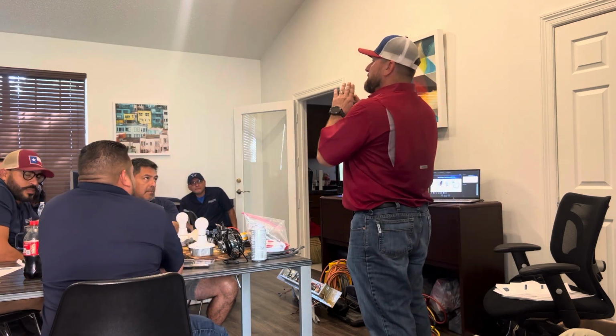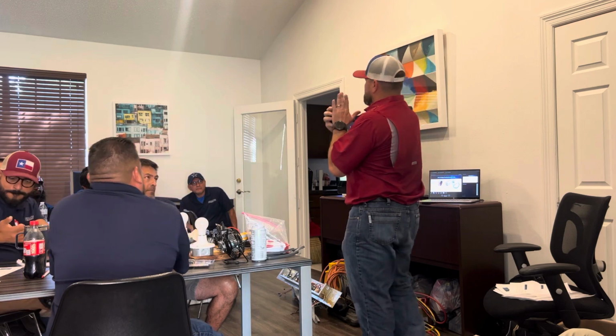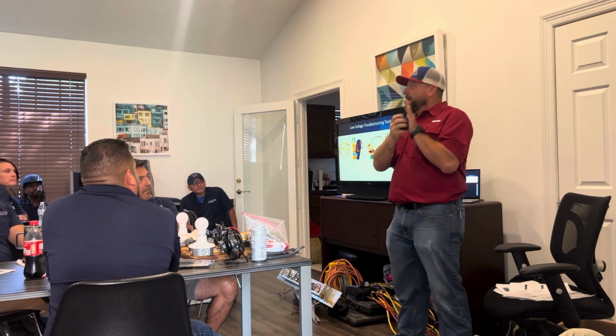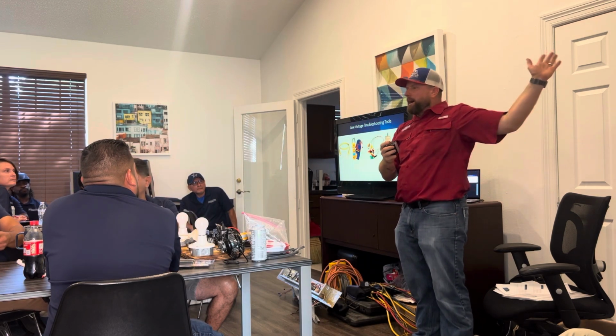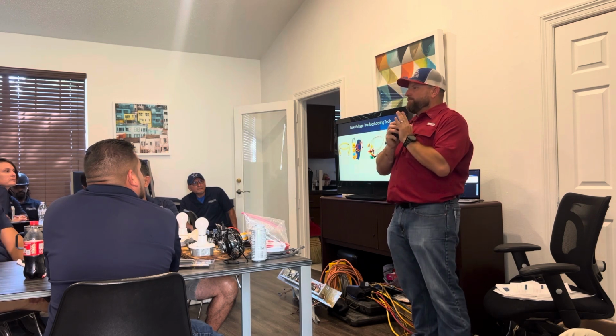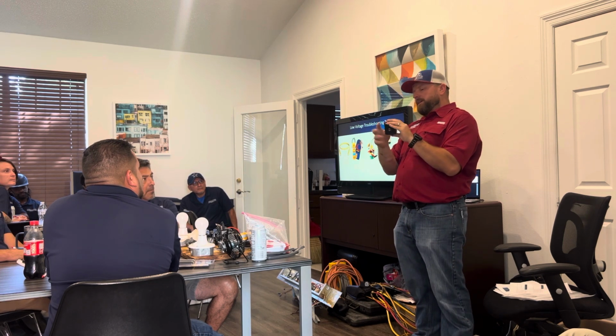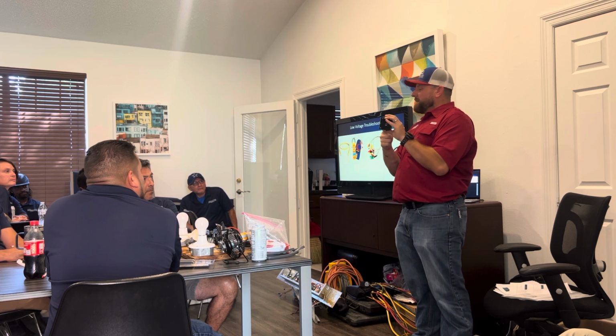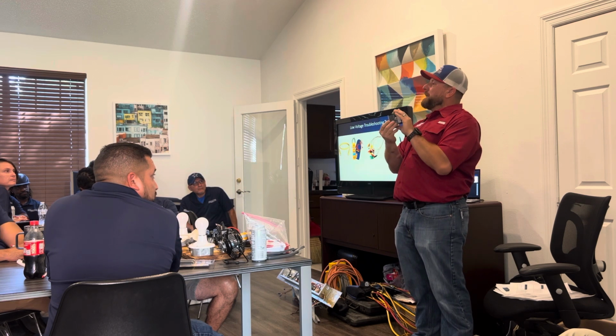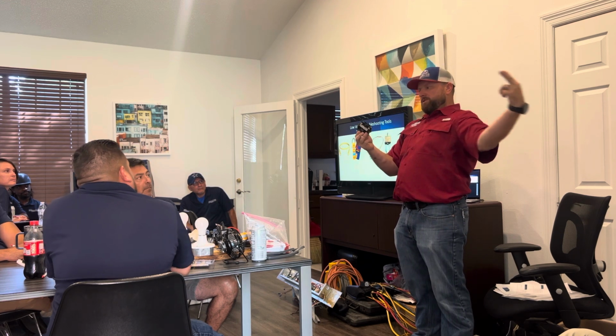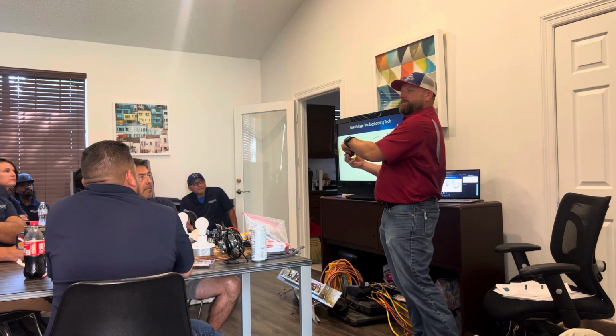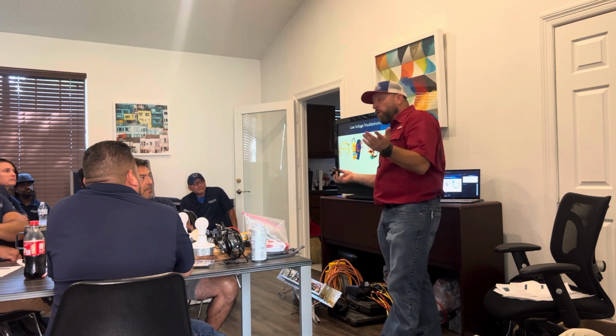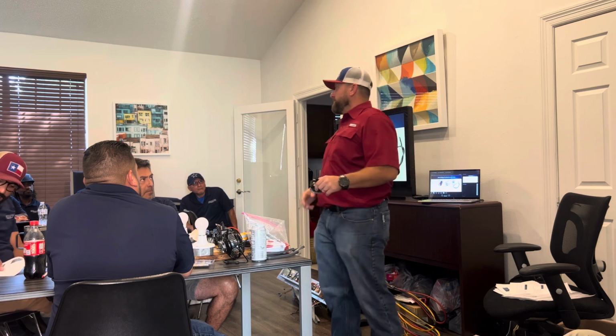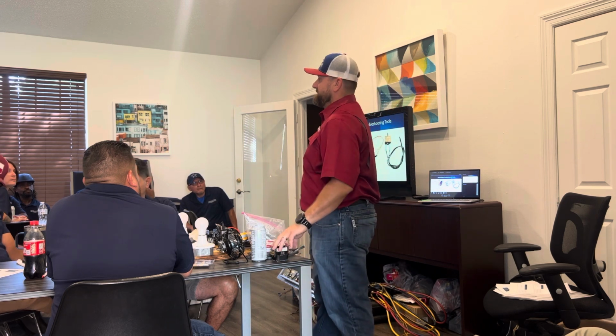So when this is connected to your condenser, it's connected to metal, right? Everything is grounded from the house or the panel. So if this little coil gets grounded to this, say this back plate, then as soon as you're getting hit with your 24 volts, it'll pop that transformer. Or if you have a fuse in line, it'll pop that fuse. Does that make sense?